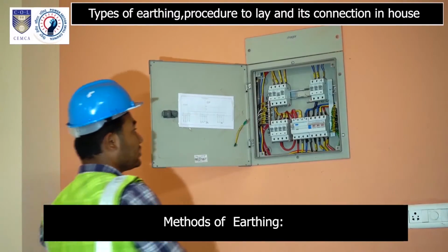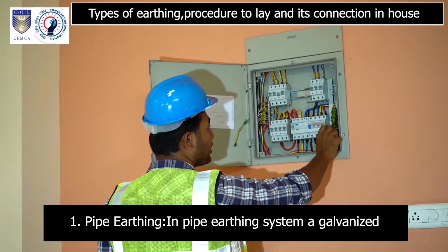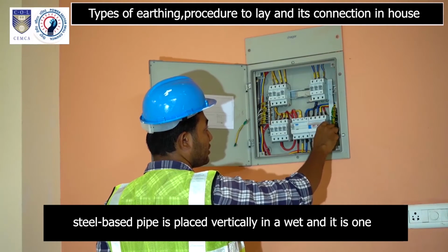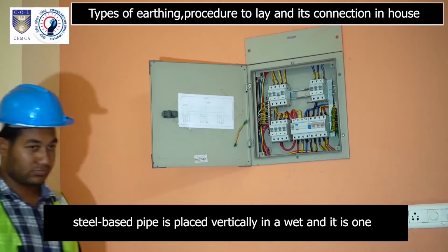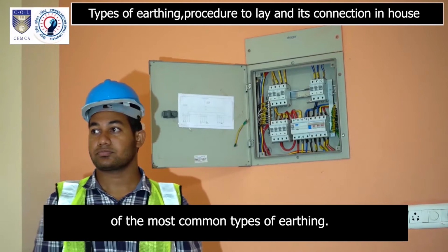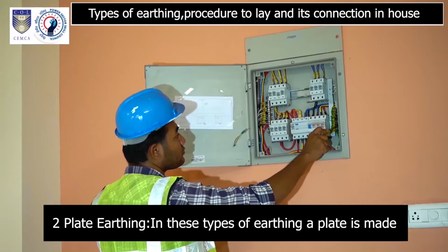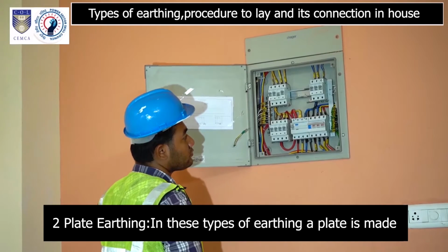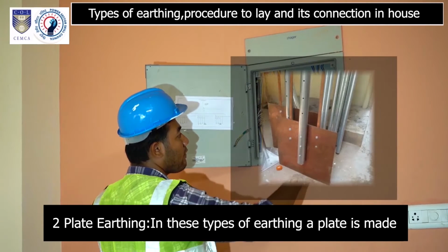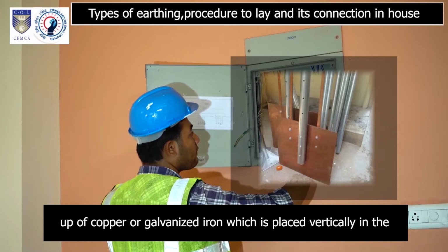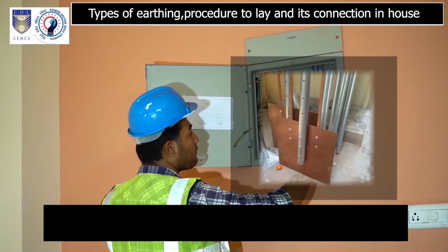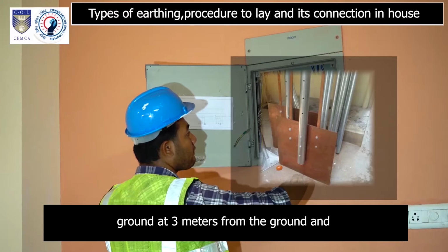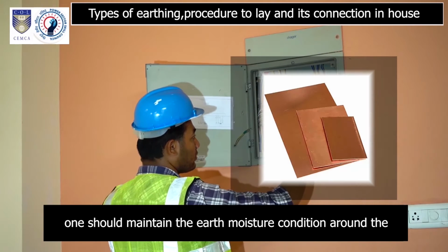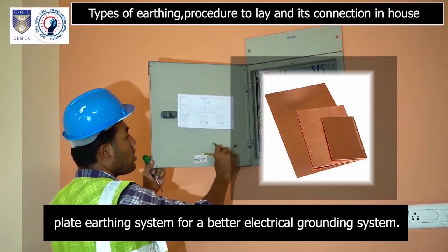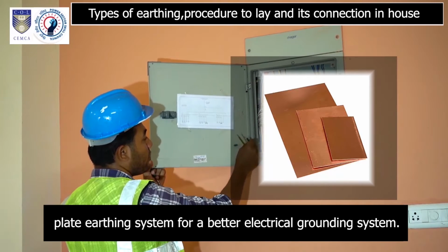Methods of earthing. 1. Pipe earthing. In the pipe earthing system, a galvanized steel pipe is placed vertically in wet soil, and it is one of the most common types of earthing. 2. Plate earthing. In this type of earthing, a plate made of copper or galvanized iron is placed vertically in the ground at 3 meters from the surface, and one should maintain the earth moisture condition around the plate earthing system for a better electrical grounding system.